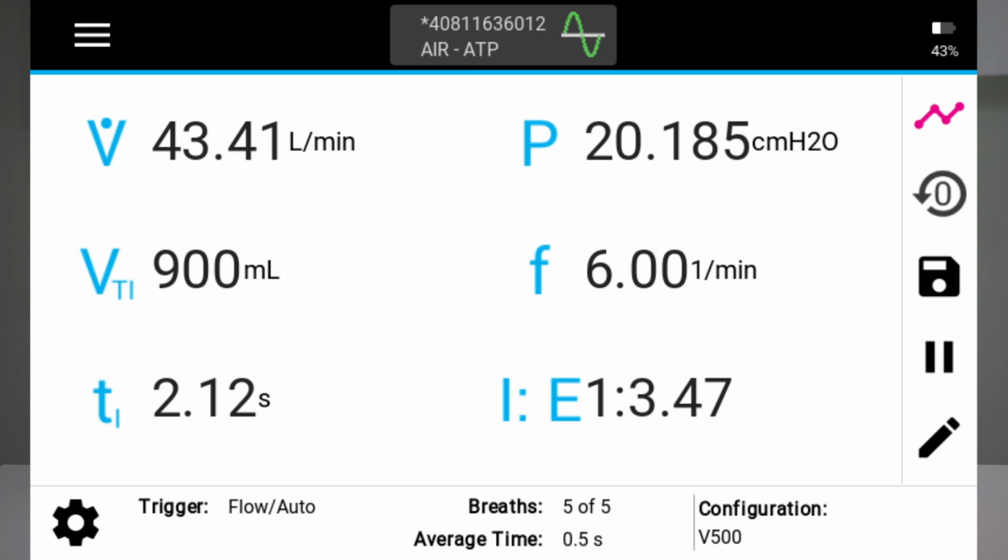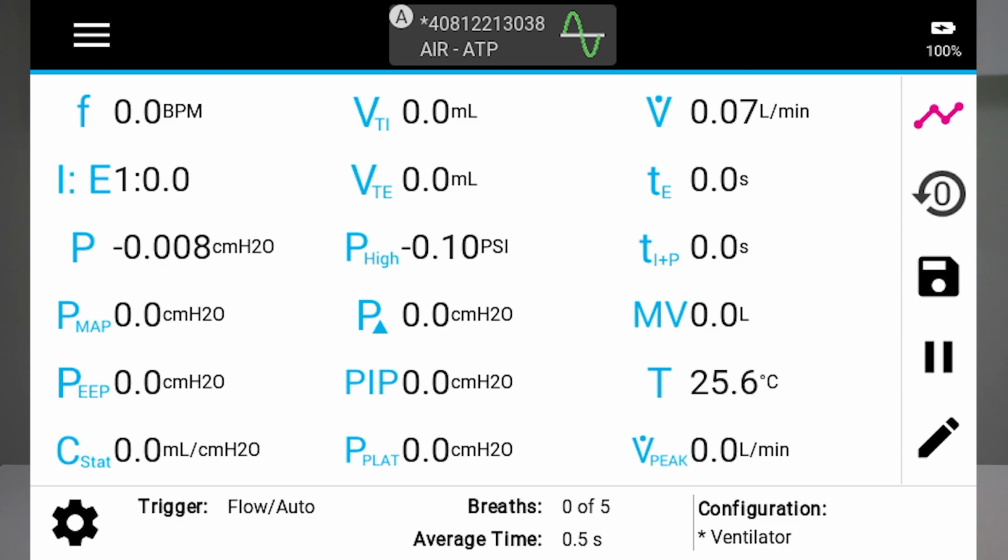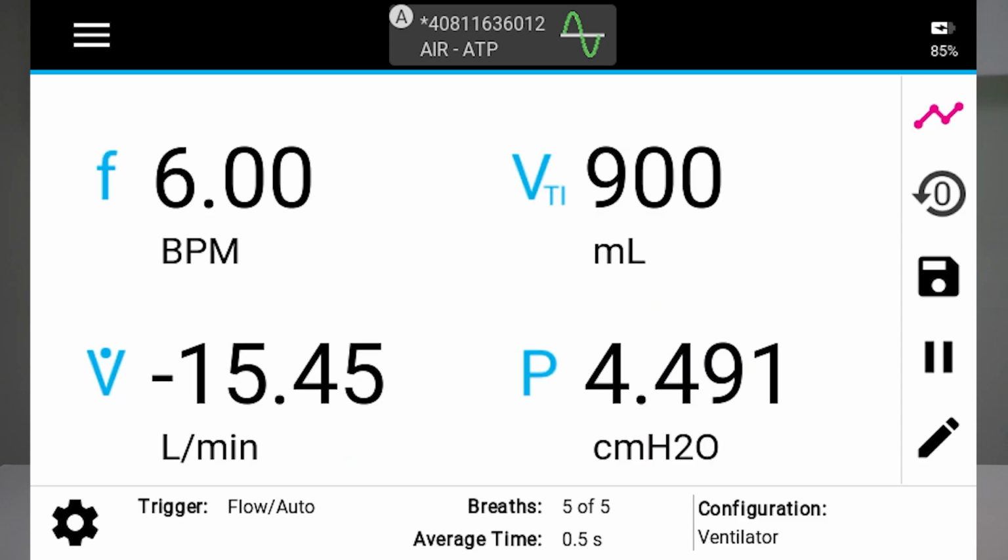Biomeds like Certifier flow analyzers because they can easily view all their measurement readings and instrument settings from a single screen. You can display up to 18 measurements at one time on the parameter screen, and the font size and positioning will automatically adjust based on the number of measurements selected. The largest font size will be displayed when 4 or less measurements are selected.